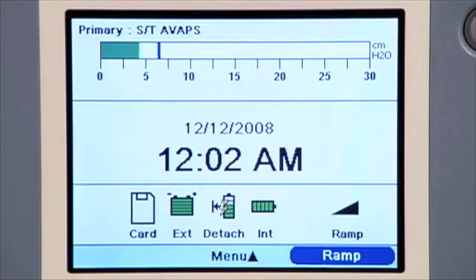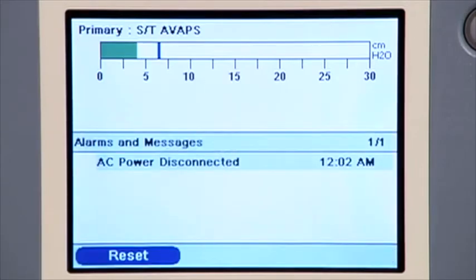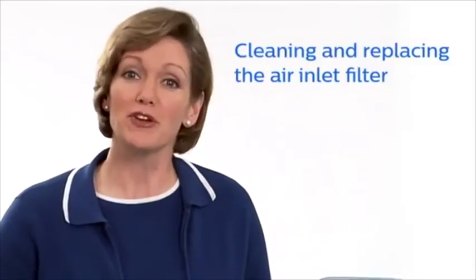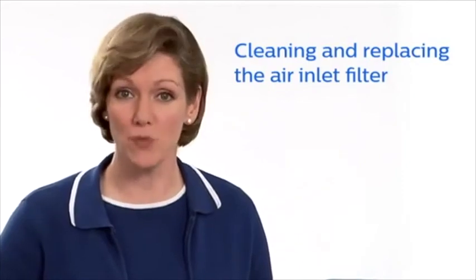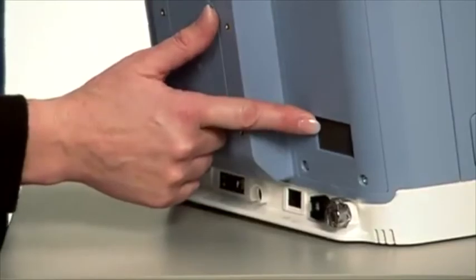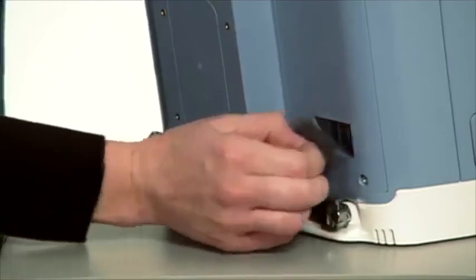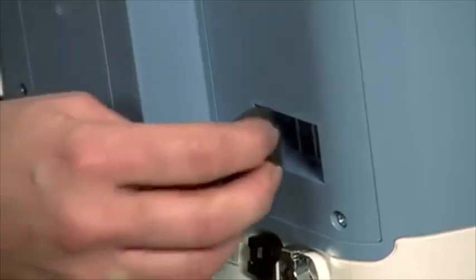Trilogy also displays informational messages and confirmation alerts that notify you of conditions that require attention. For example, the AC power cord is unplugged, or the battery is no longer charging. You will hear a single beep when an informational message appears on the display screen. With normal use, the gray foam filter should be cleaned at least once every 2 weeks. The filter is in a recessed area on the back. Remove it by gently squeezing the filter in the center and pulling it toward you. Insert a clean filter to take its place.